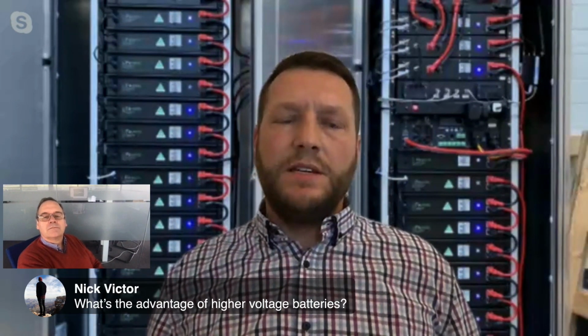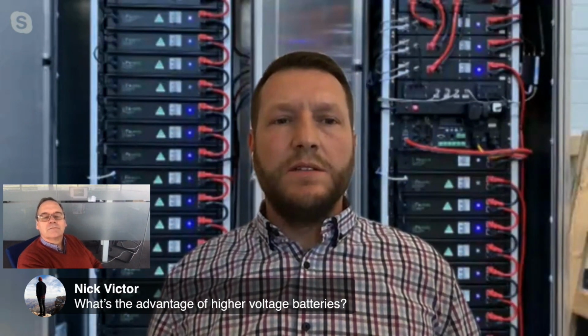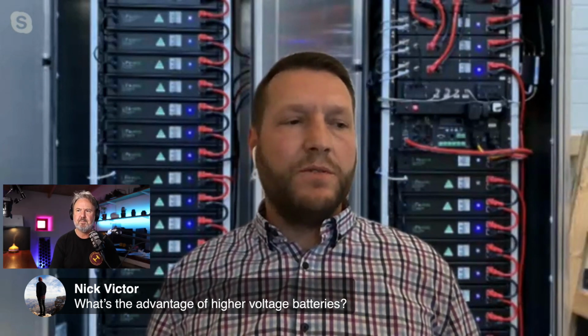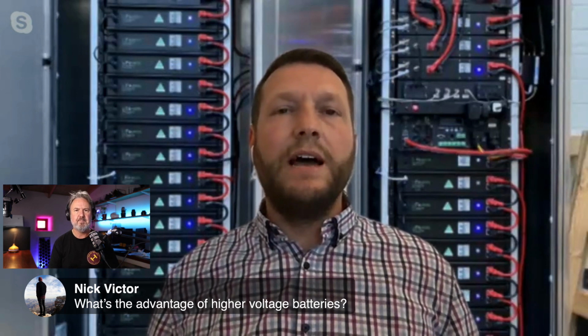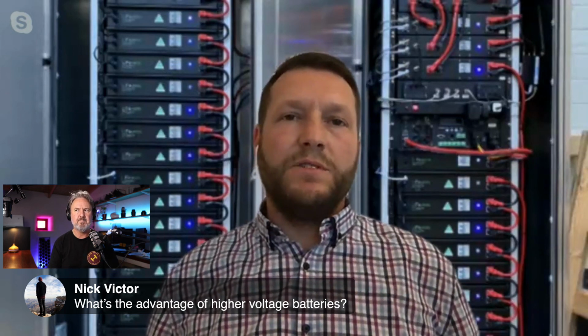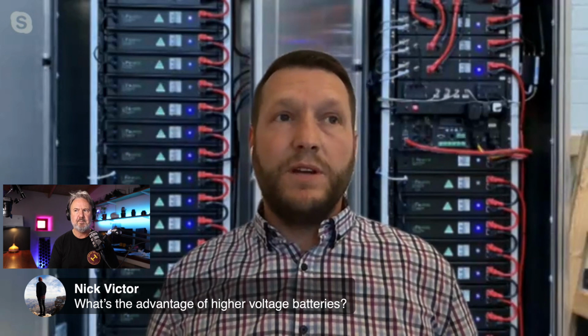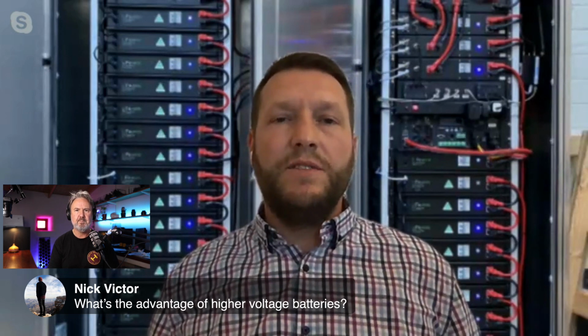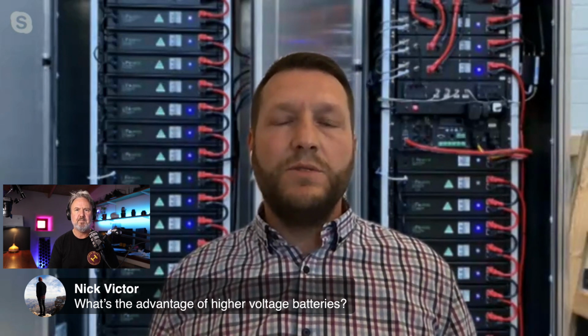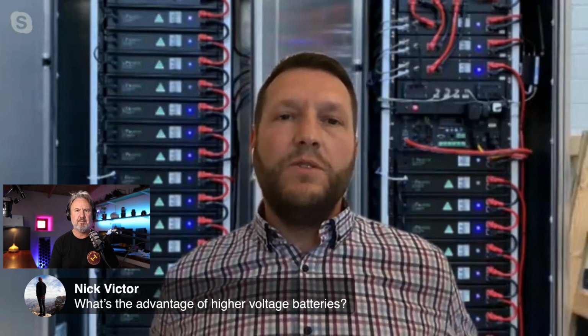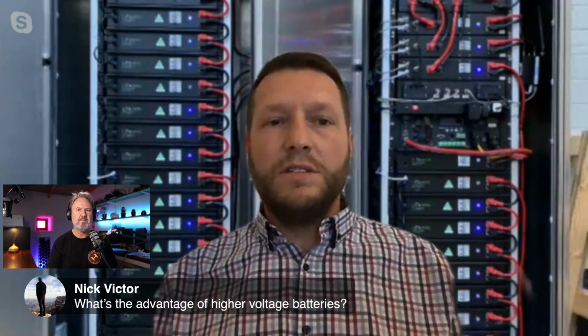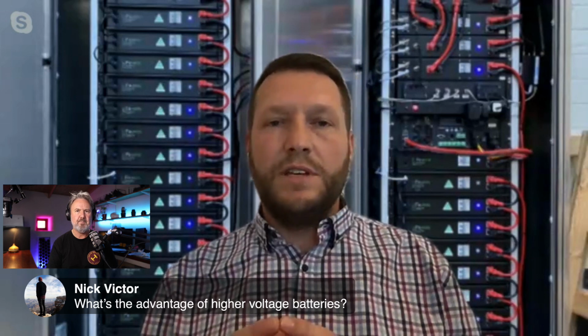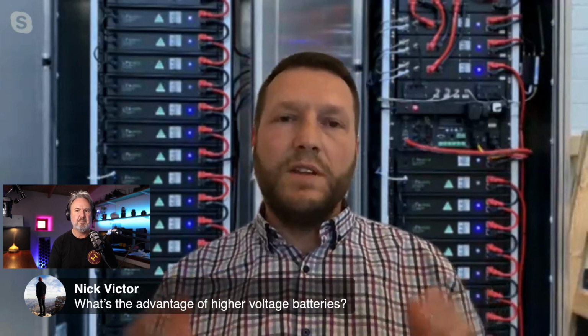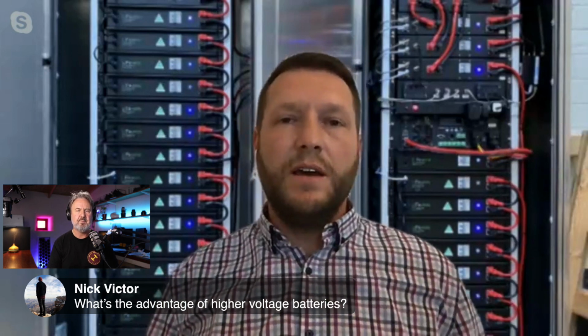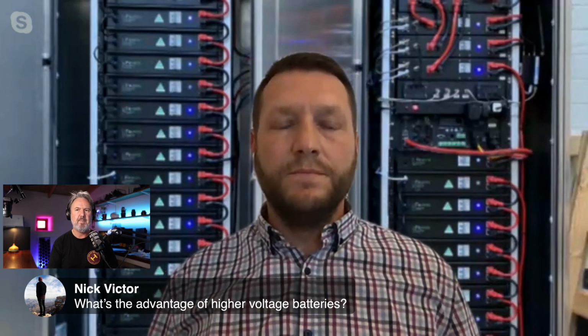One of the main advantages is you're dealing with smaller currents. If you imagine running 1,000 amps at 48 volts, that's some pretty heavy-duty cable you've got to have. But if you're dealing with the same energy at a higher voltage, your currents come down. So rather than using big contactors, you can use relays, and rather than thick cables, you can use thinner cables. It really comes down to current.